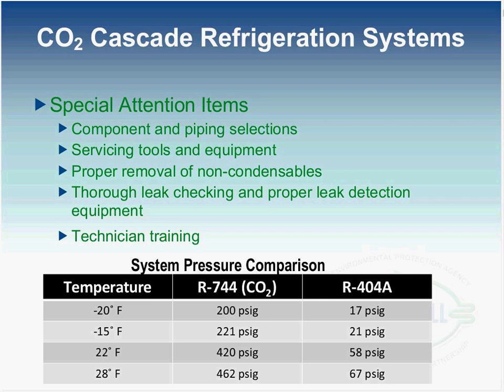Okay. No problem. Then you're also going to want to make sure that you have the proper leak detection and protocols in place, because typically the leak detection materials that are used for standard DX systems are not going to be utilized in CO2 systems. It will require different equipment and processes to a certain extent. And then, obviously, this is a relatively new technology. So one of the key things is ensuring that all technicians and service people are actively trained on this technology so they don't find a surprise when they show up to a job site.